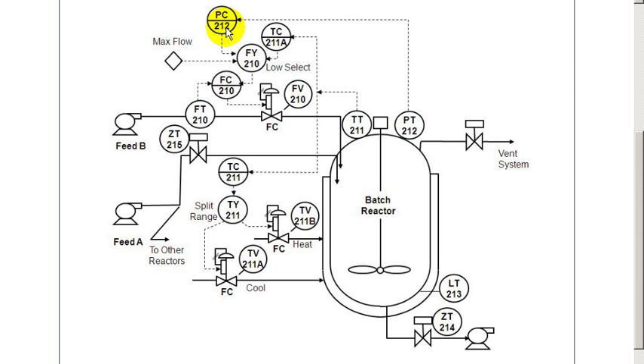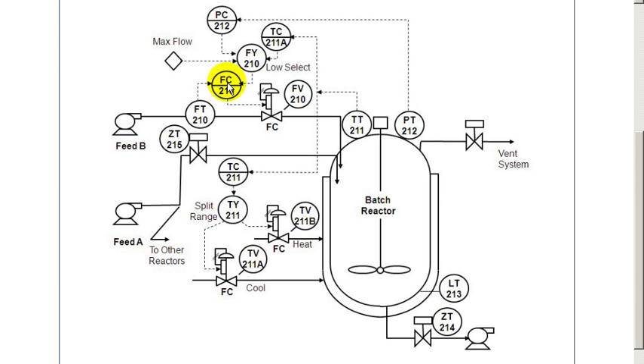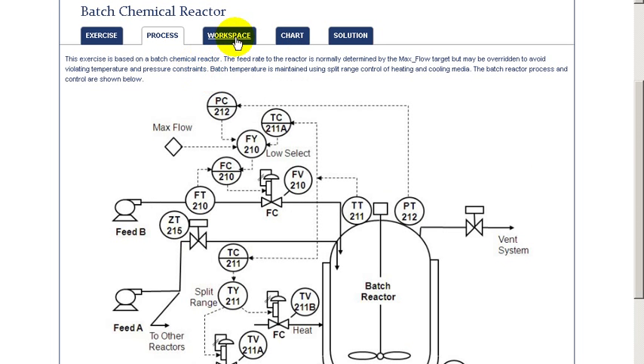There's an override on pressure and temperature to keep those from exceeding some constraint limit on the operation of the process. So our selector is a low selector in that case, so the lower of the three is then selected in the control of the second material to the unit. After the batch is complete, then a valve is opened and the batch contents are then dumped.